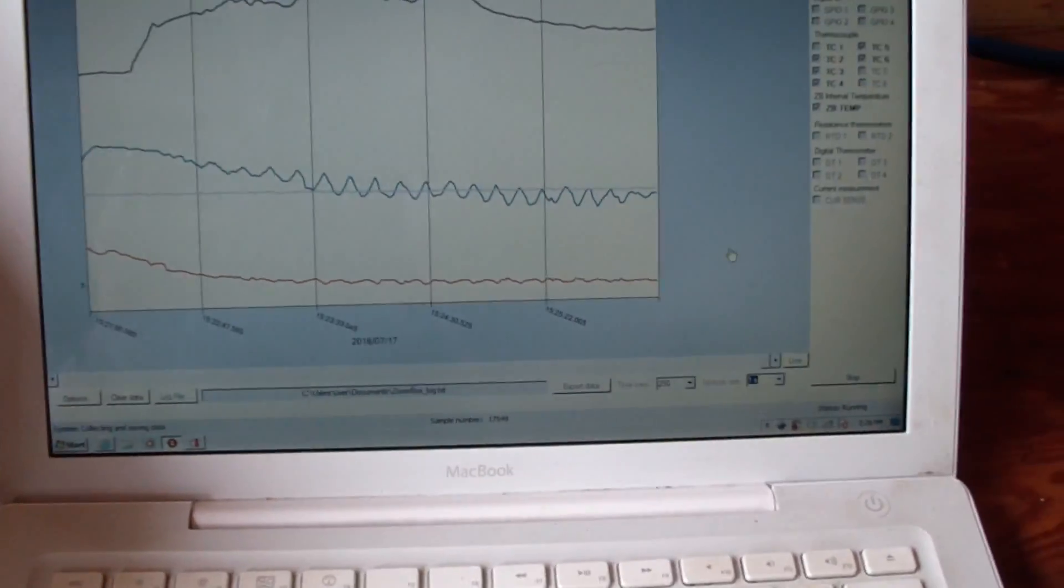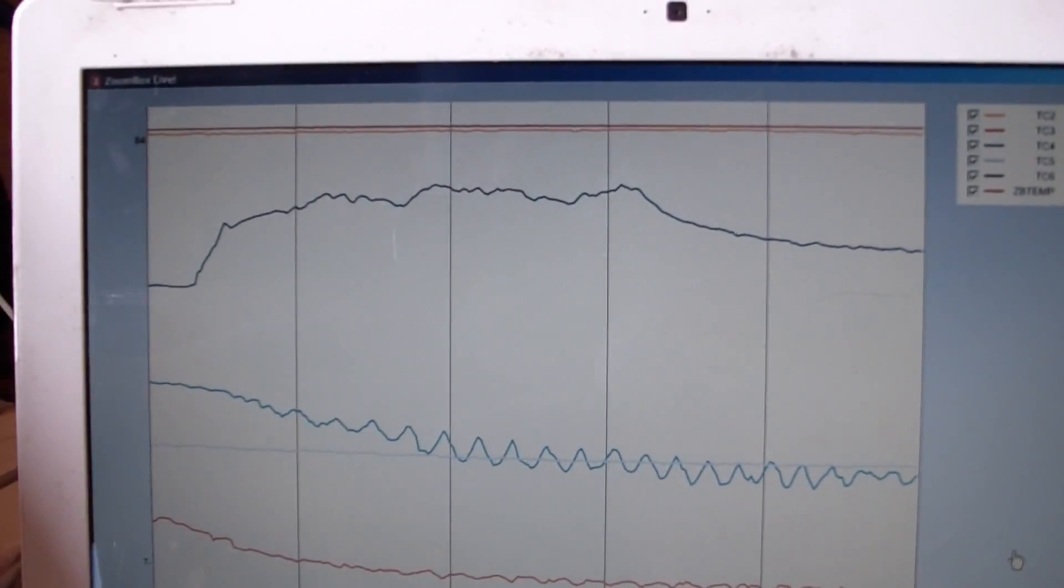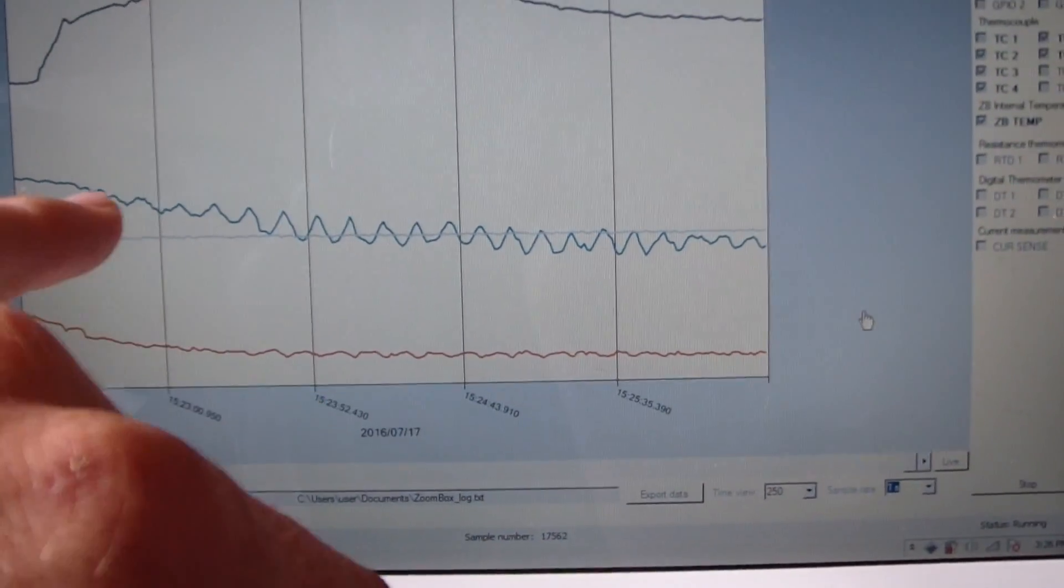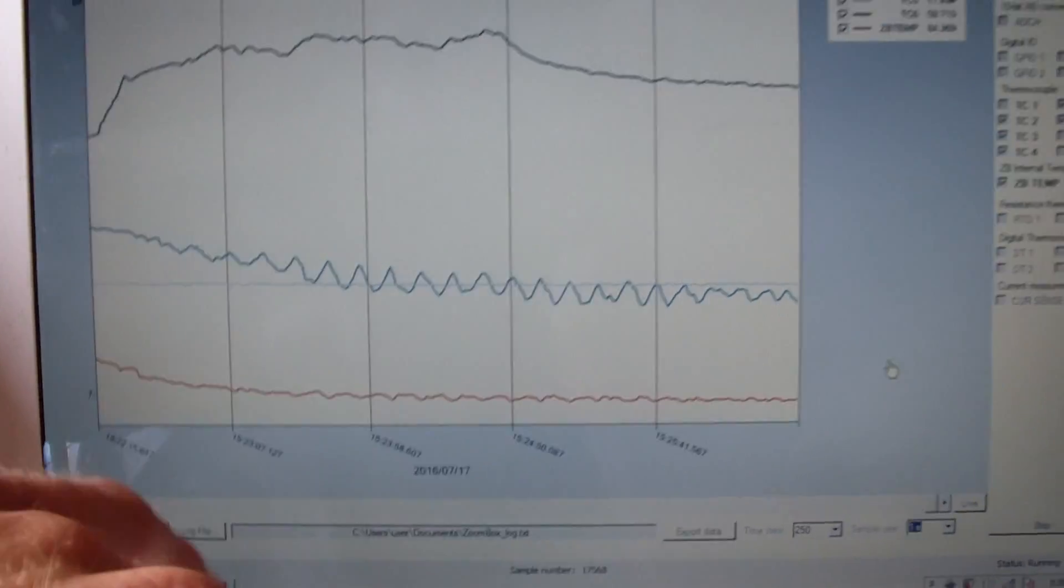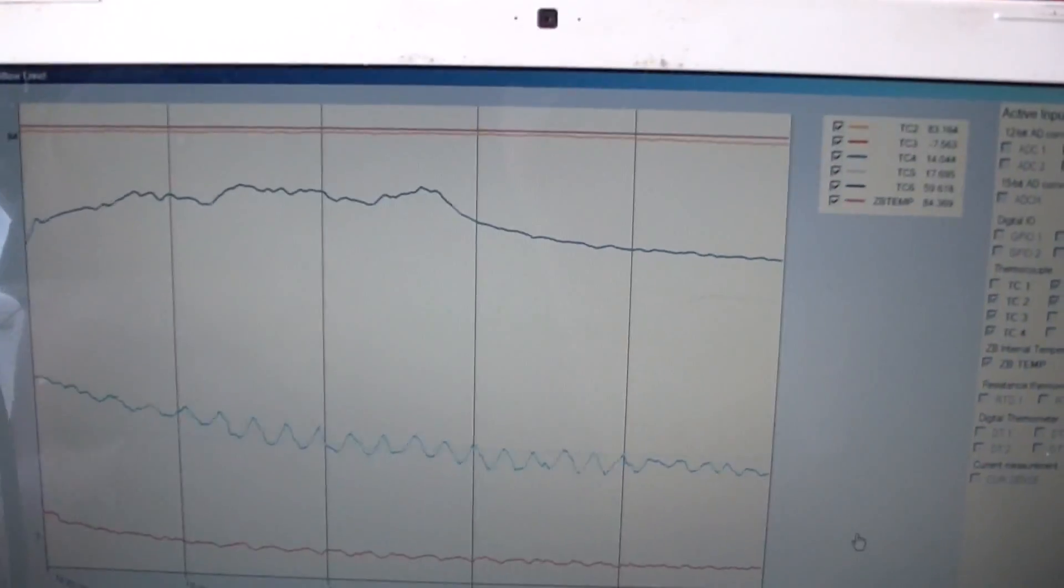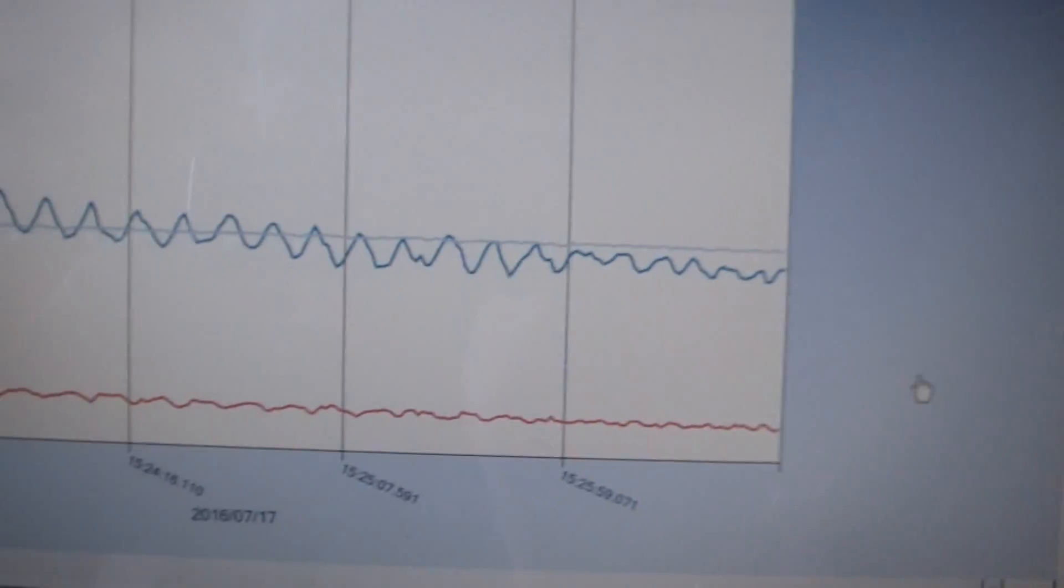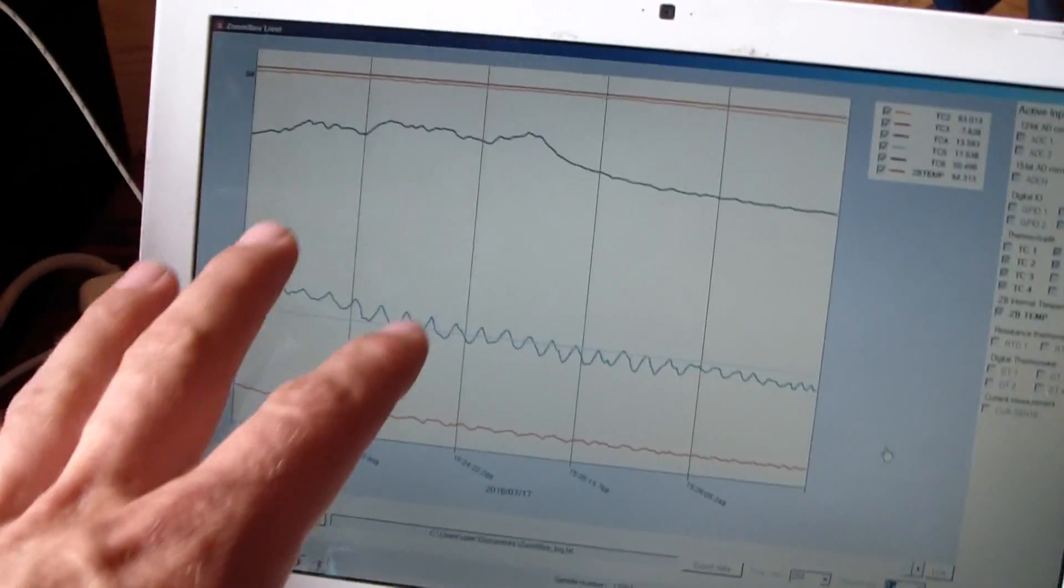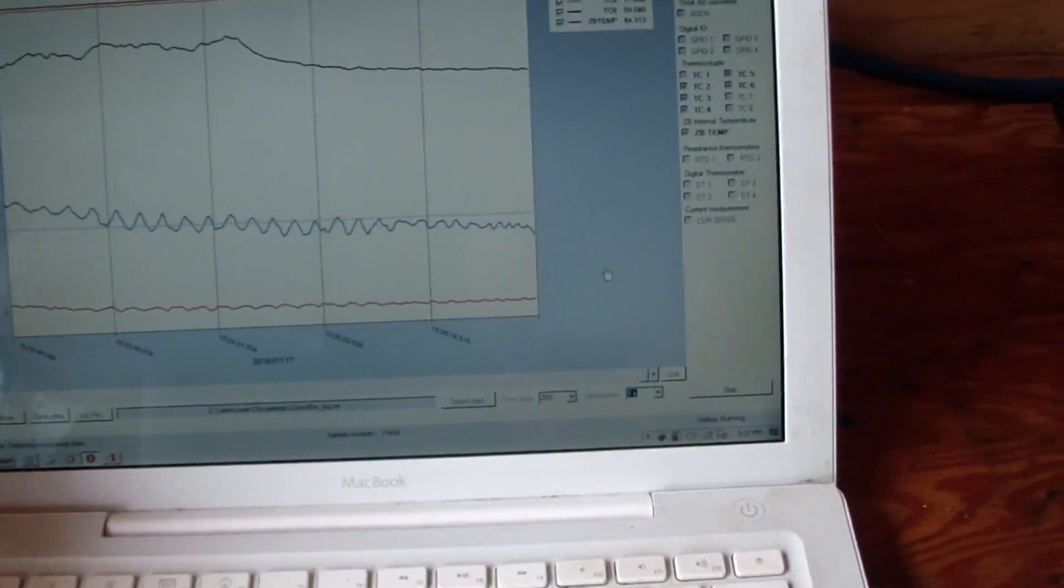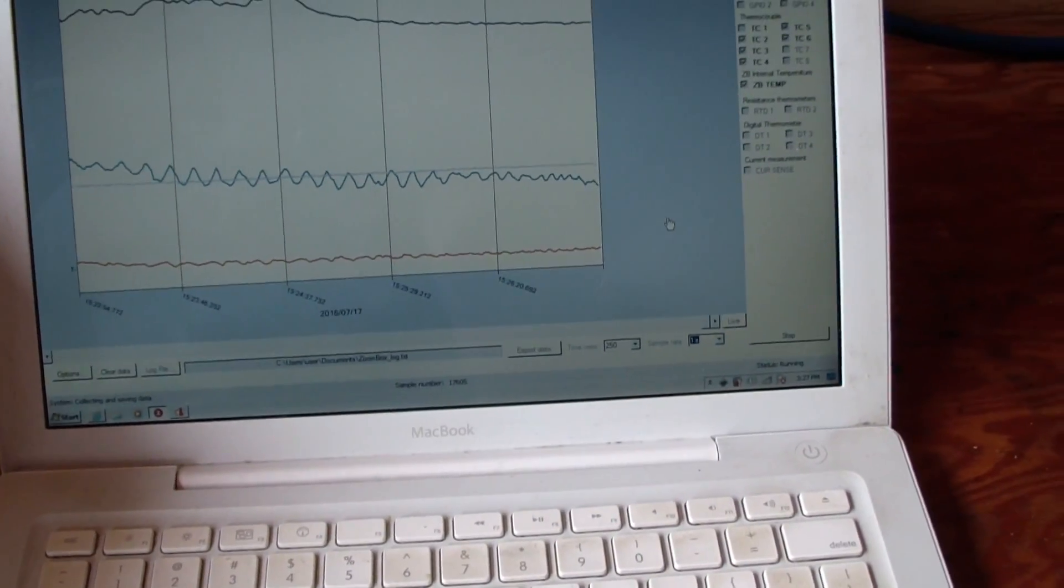I've only ran this for a little while. It's definitely very interesting already. A couple of things to keep in mind: that dark blue line there is the air temperature inside. This lighter blue line is after the heat interchanger. The red line is before the heat interchanger, the superheat coming off the evaporator. I can change the time scale and it shows a little more detailed information. These two lines up here, one of them is ambient air. There's a temperature sensor inside the Zoom box and the other one's a subcoolant, so they stay pretty close. There's a lighter line there and that's actually the coolant temperature that runs through there. There's more information I don't have the superheat on here because it'll auto scale and it'll shrink all this information down. There's going to be some more temperature sensors installed once I get the baffle in. I'll establish the way that I'm going to collect my data and analyze it, sample rate and all that kind of stuff.